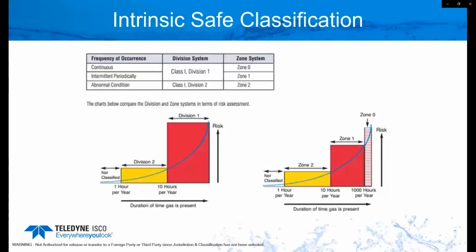If you look at what is a Class I Division I environment, there's also the zone system, which would be more international. In the US, we look at Class I, Div I and Div II. Division II would be an abnormality—maybe something happened that caused a spill of hazardous material that could cause an explosion, and that would be under a Class I Division II rating.